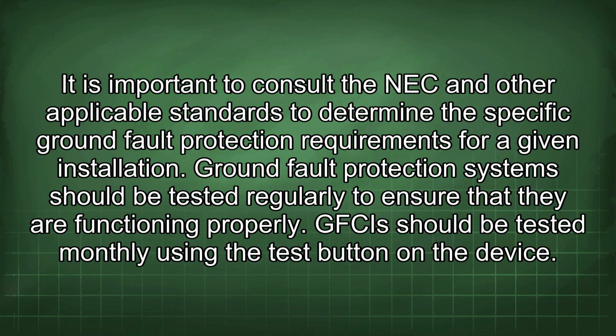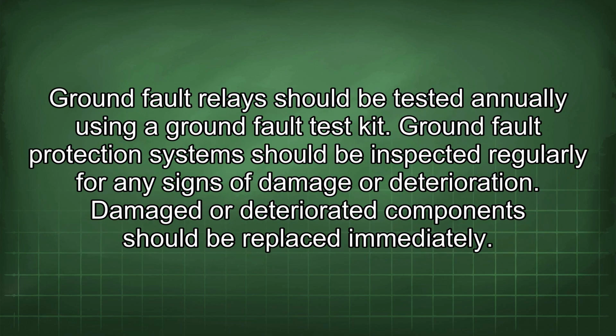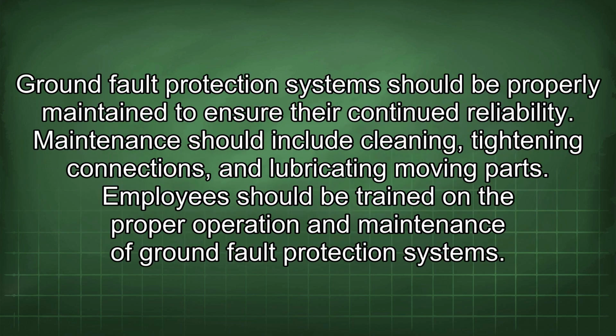Ground fault protection systems should be tested regularly to ensure that they are functioning properly. GFCI should be tested monthly using the test button on the device. Ground fault relays should be tested annually using a ground fault test kit. Ground fault protection systems should be inspected regularly for any signs of damage or deterioration. Damaged or deteriorated components should be replaced immediately. Ground fault protection systems should be properly maintained to ensure their continued reliability. Maintenance should include cleaning, tightening connections, and lubricating moving parts.